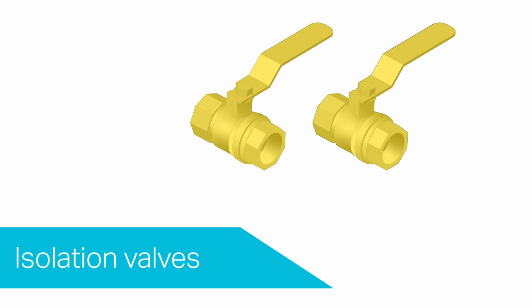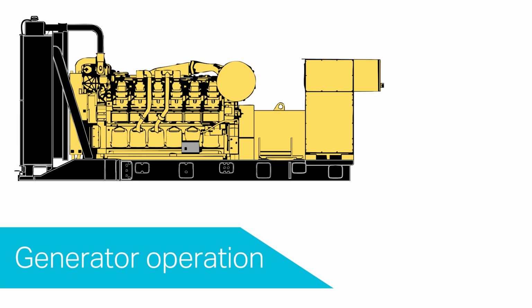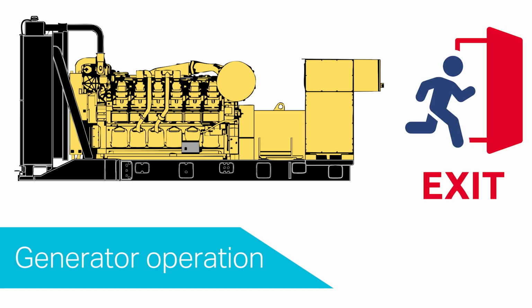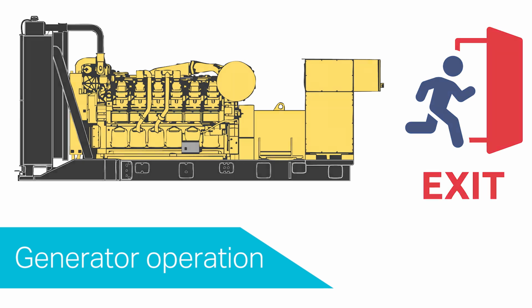Hotstart recommends the use of isolation valves at the inlet and outlet ports to facilitate maintenance and servicing of the heater. Ensure valves are closed during maintenance and opened afterwards to allow coolant to flow to the heater before startup. The generator does not need to be removed from service to perform the retrofit. For your personal safety, exit the area if the generator energizes while you are performing heater maintenance.